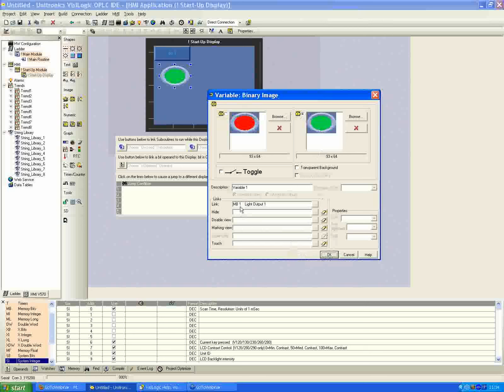The display during programming simply reflects the last radio button clicked before you hit OK. We've defined the memory bit link for our graphical representation. The toggle button checkbox, if selected, will automatically toggle the state of the linked memory bit whenever you physically touch this variable on the HMI screen — without any ladder code. If you leave it unchecked, the state is dependent on a condition in the ladder code. In our case we're not using the toggle, so I'll just click OK.